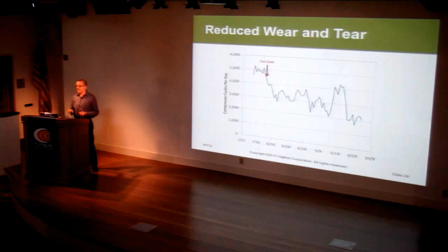If you cycle a lot, if you cycle enough, you end up with what's called short cycling. Short cycling has two problems. One is that if you short cycle a lot, you can have a situation where you end up sucking liquid refrigerant into the compressor. Most compressors aren't able to withstand that, and it will cause catastrophic failure of the compressor. The other thing that happens is the oil that lubricates the compressor is carried around by the refrigerant. So if you short cycle the compressor, the refrigerant doesn't reach a stable equilibrium where it allows the oil to move completely around the compressor and lubricate it. So the short cycles effectively cause the compressor to be operated without lubrication. And that obviously wears out compressors a lot faster.